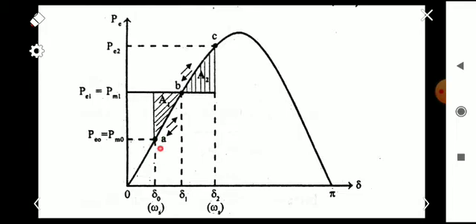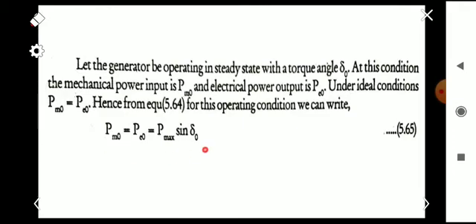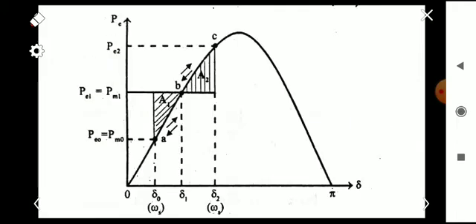Point A on the power angle curve is the steady state operating point, where P = P0 = Pmax × sin(δ₀). The ideal condition assumes mechanical power input equals electrical power output. At this operating point with torque angle δ₀, the rotor speed equals synchronous speed ωs.